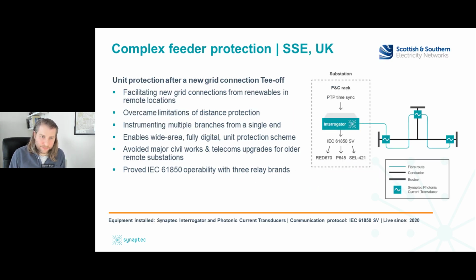Here in Scotland, we've deployed a system which performs single-ended differential protection on a 132 kV circuit. A single fiber is able to collect local and remote CT measurements, in this case over about 50 kilometers. These are then brought back to a central location to perform the protection function. All of these measurements, even from 50 kilometers away, are available centrally in less than 1 millisecond. Typically it's faster than that, but 1 millisecond is usually the limit.